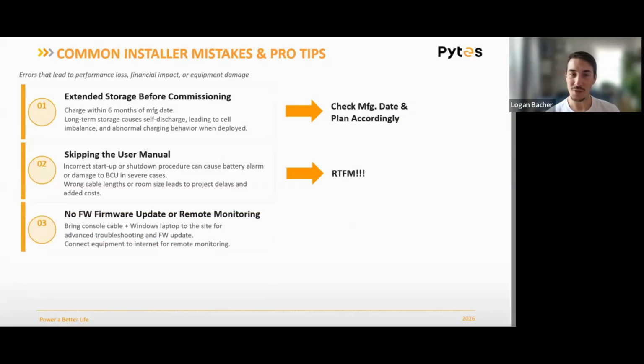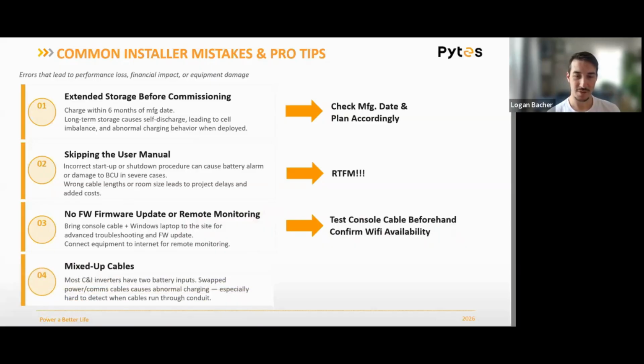Not doing firmware updates or skipping the remote monitoring setup is really, really important too. When we deploy these systems, during commissioning you want to take that extra time to update the firmware, both on the battery and inverter side, to the latest version. I think that's best practice for any system, commercial or resi. You want to make sure you're prepared to do that update either on site with a laptop and our console cable, or if you can connect the batteries to the internet, just like the inverter, we can often do that update remotely. This one's super important - I know it may not seem as critical as getting the system turned on and going, but we want to make sure it's going to work without issues long term. So take that extra little time at the site to get those tasks completed.